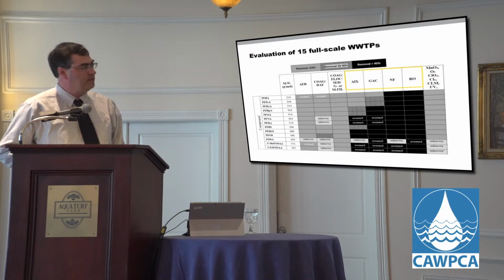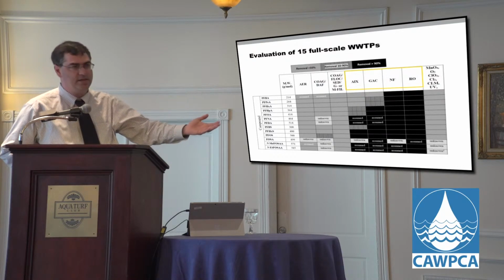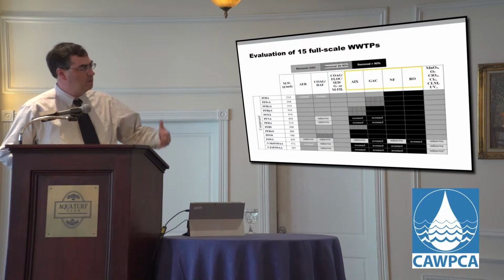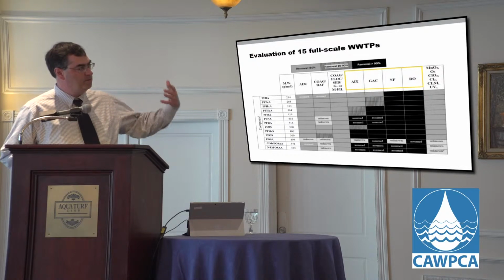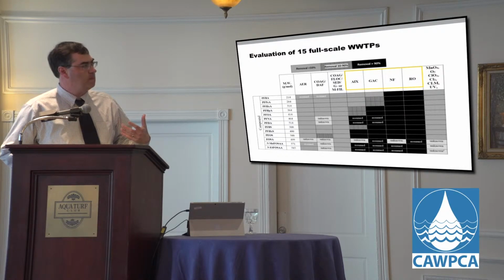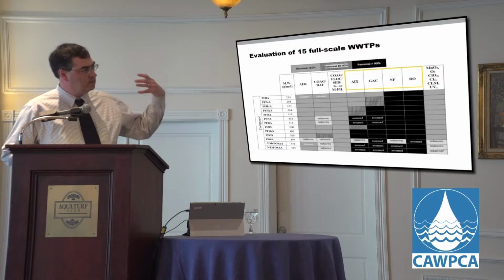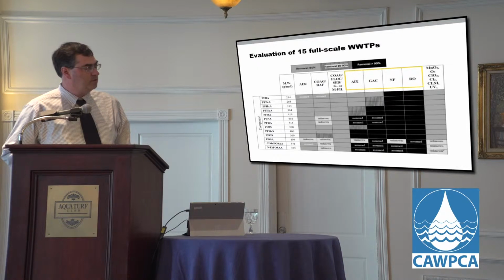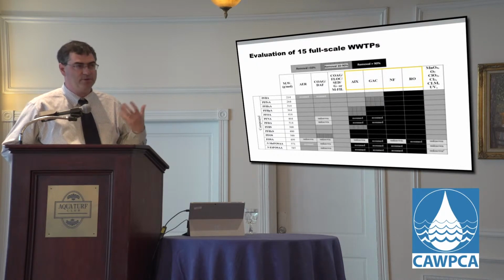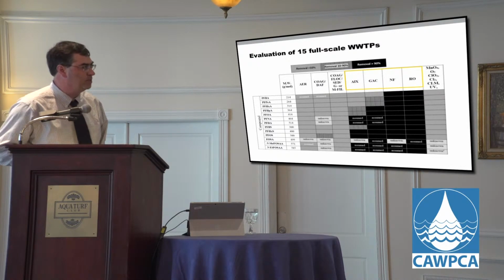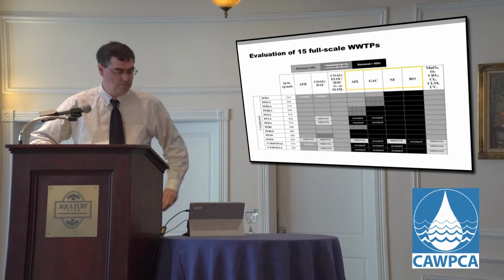And you can see that the nanofiltration and reverse osmosis, they're very effective at taking out PFAS. The next level would be granular activated carbon, and then the next step below that would be ion exchange. The other processes up there perhaps could be used for pre-treatment, but you're looking at things like coagulation, which are really seen more as a pre-treatment step.